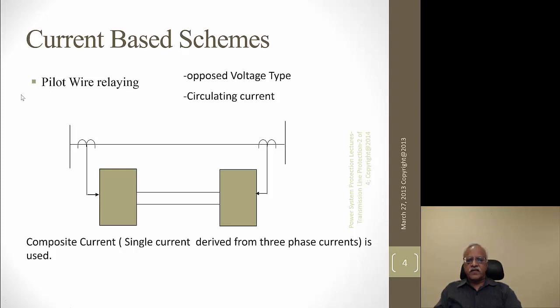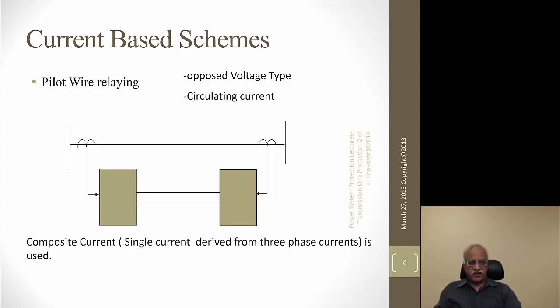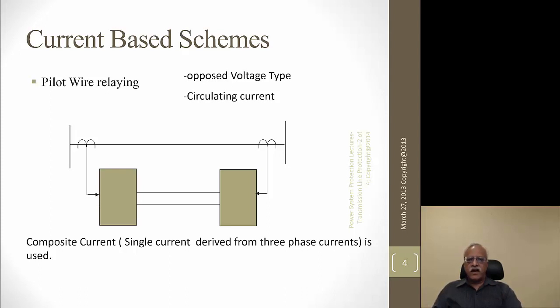In pilot wire schemes there are two types: opposed voltage type, where voltage is generated based on currents at the remote end and they look at how they are balanced; or the circulating current principle. As mentioned, it could also use composite current — a combination of all three phase currents — and only one composite current is sent from station A to station B. Station B also sends similar information back to station A.